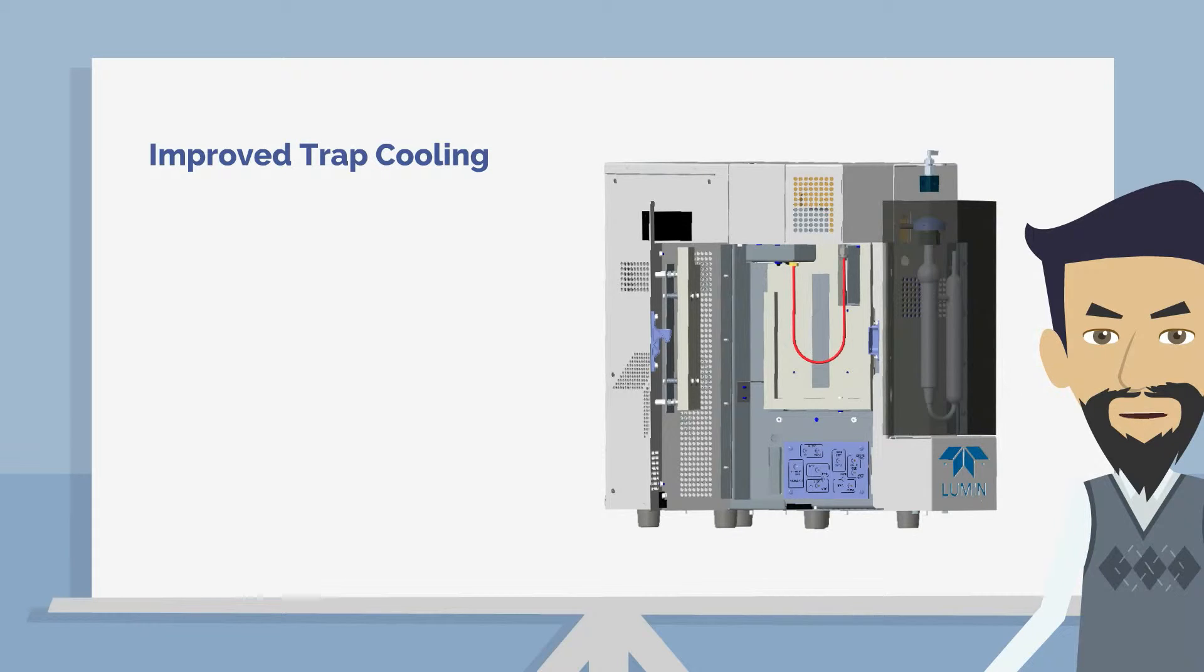One of the new features is improved trap cooling performance. Unlike previous models that pulled air from within the concentrator for trap cooling, the Lumin pulls air from outside the unit, improving its cooling efficiency.